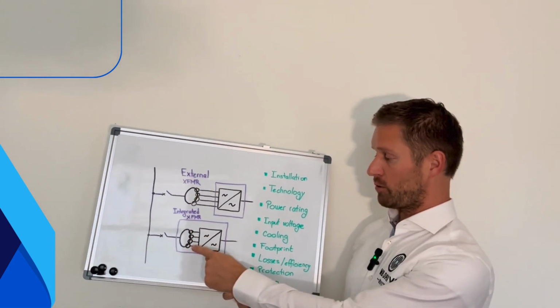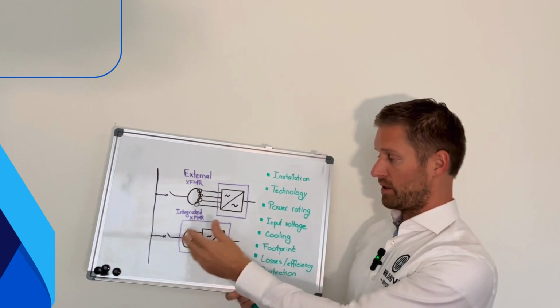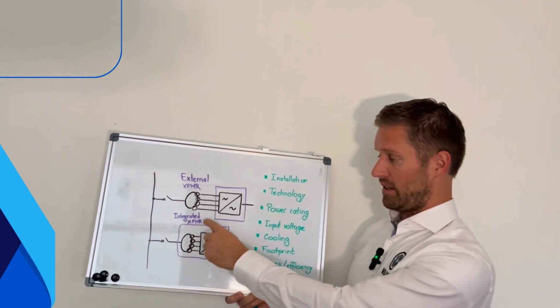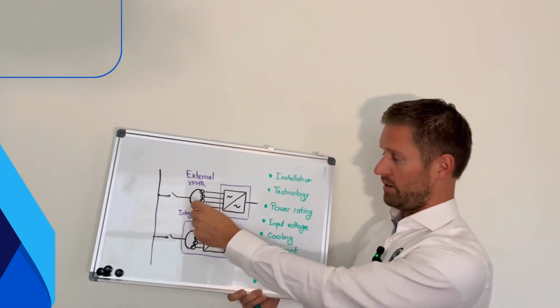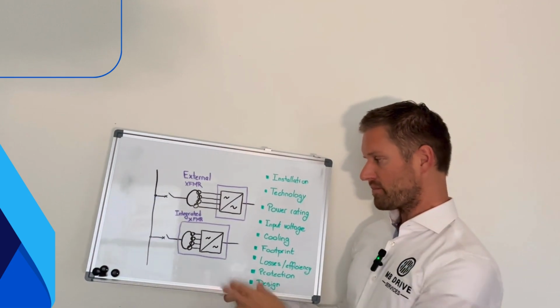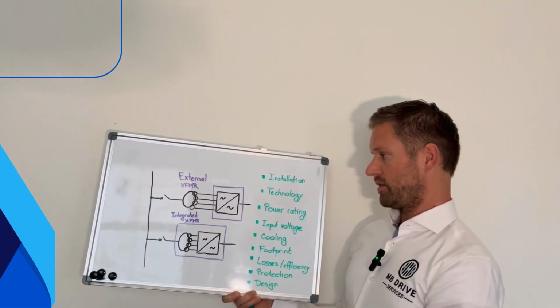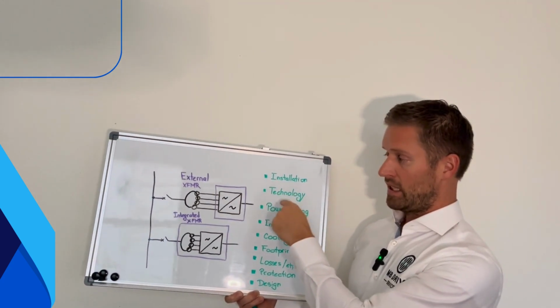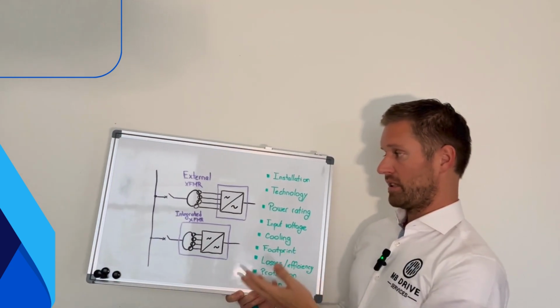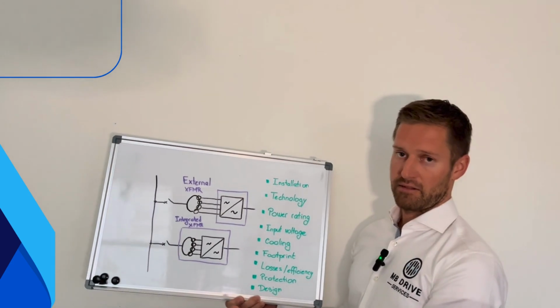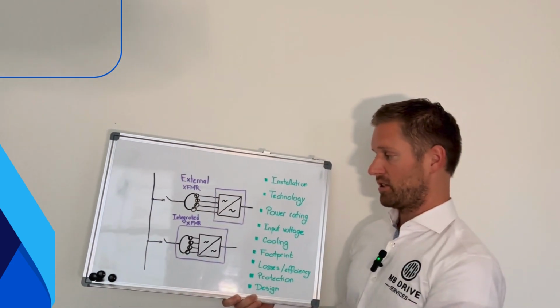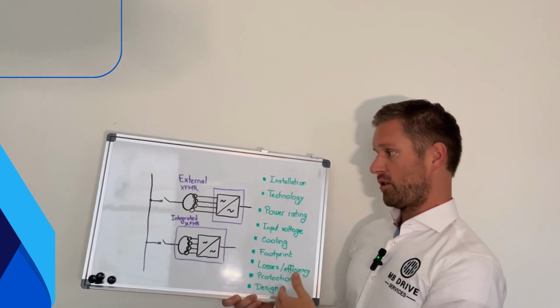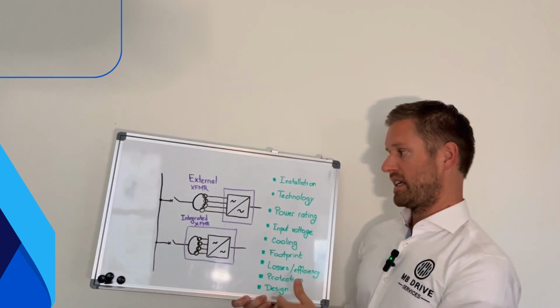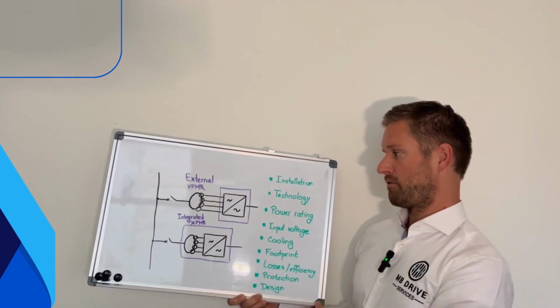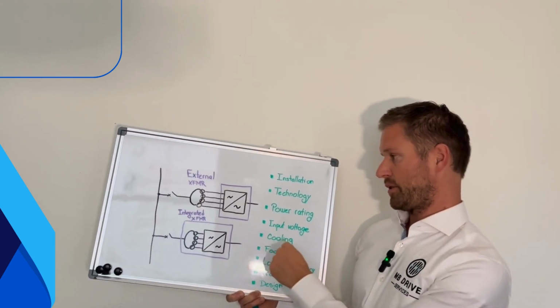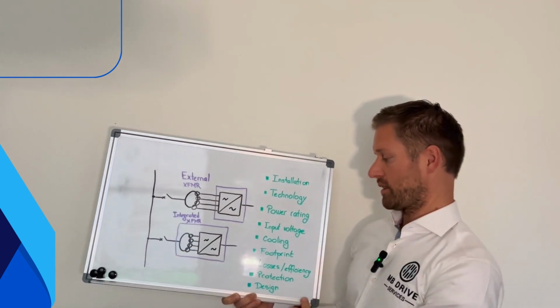Cooling: the input transformer is usually air forced, so it's dry type, cooled with air, and there is a cooling fan typically on the roof of the enclosure. So cooling fan for the transformer, cooling fan for the VFD. So air forced is the typical cooling method. On the external transformer, it depends on the technology, if it's dry or liquid immersed type, but we have practically any type of cooling: AN, AF, AFWF, those with a heat exchanger, or on the liquid side, ONAN, ONAF, OFWF, or KNAN if it would be with less flammable liquid, and so on. So also on the cooling we have the full flexibility on the external transformer.